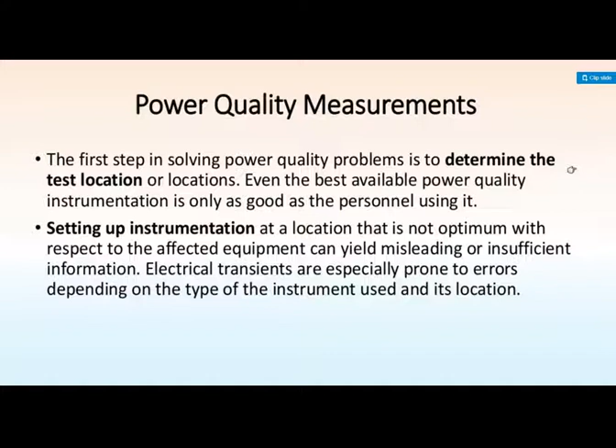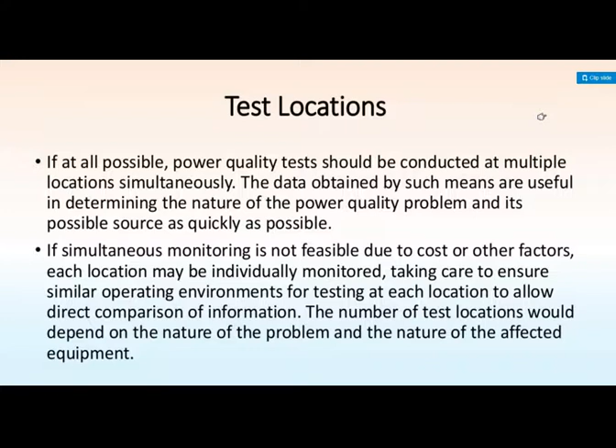Now, test location. If at all possible, power quality tests should be conducted at multiple locations simultaneously, and the data obtained by such means are useful in determining the nature of the power quality problems and their possible source as quickly as possible. If simultaneous monitoring is not feasible due to cost or other factors, each location may be individually monitored, taking care to ensure similar operating environments for the testing at each location to allow direct comparison of the information. The number of test locations depends on the nature of the problems and the nature of the affected equipment.